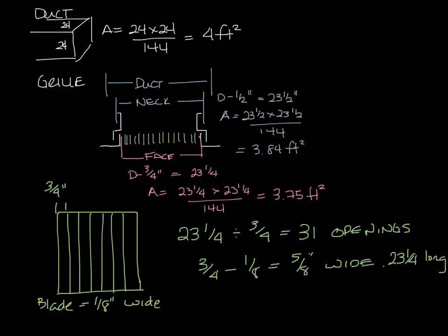So now the area that you can see through this grill, if you will, is five eighths times 23 and a quarter divided by 144 times the 31 openings, which is 3.13 square feet.